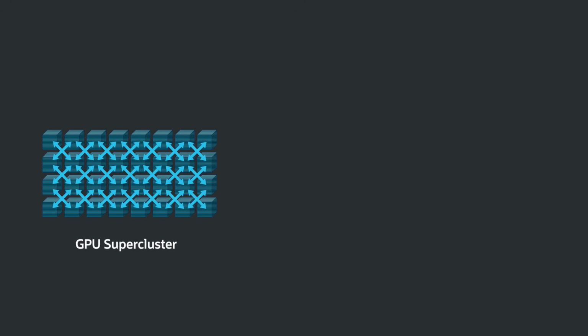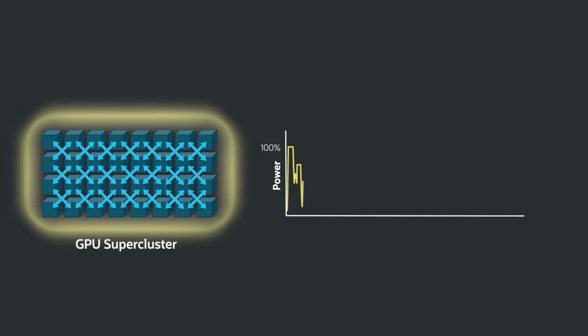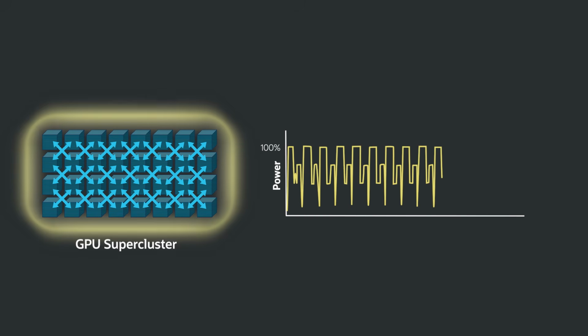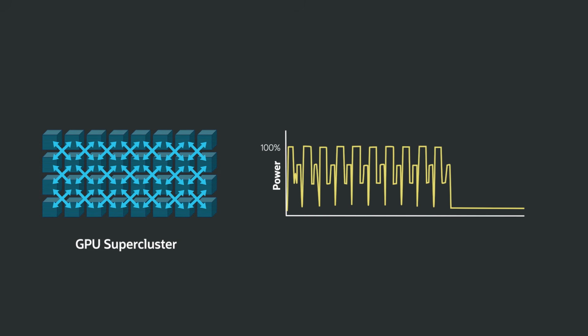That can vary from utility to utility based on the generating equipment source. They tell you what ramp rate they can tolerate, and based on that, we have to slowly go up. But AI workload doesn't go up in a step fashion. It goes instantaneously to 100%. So that's the challenge we have to solve at the data center level.